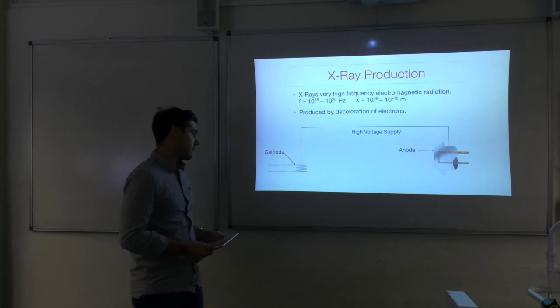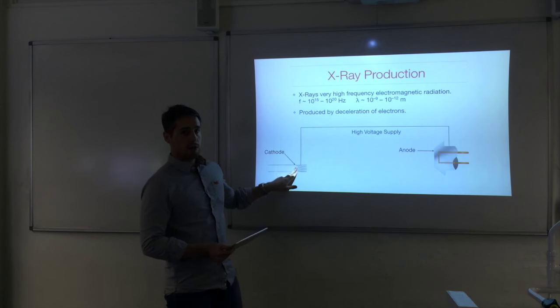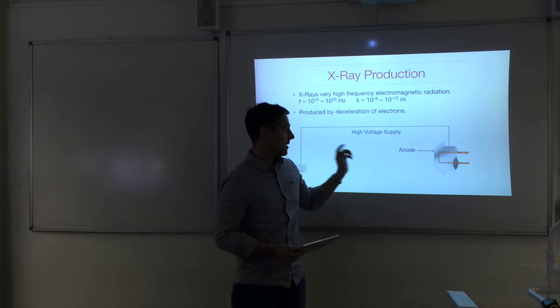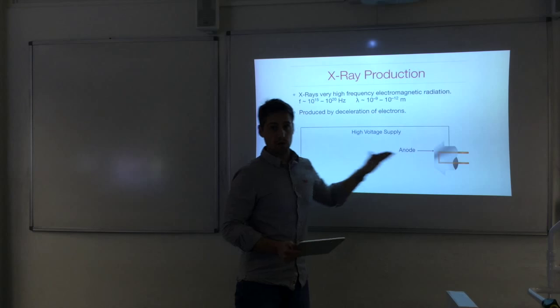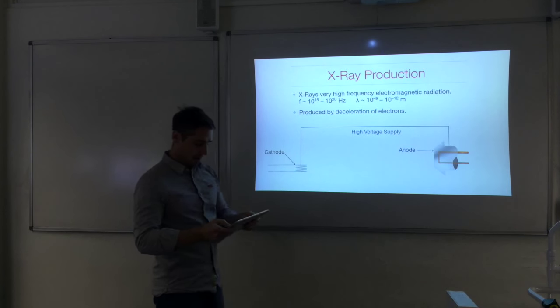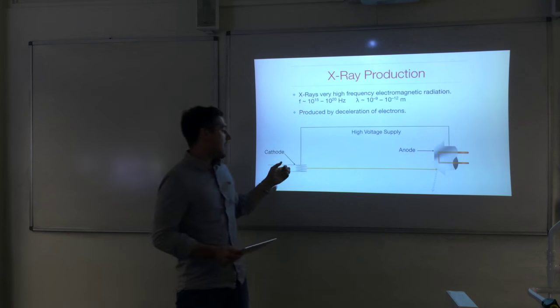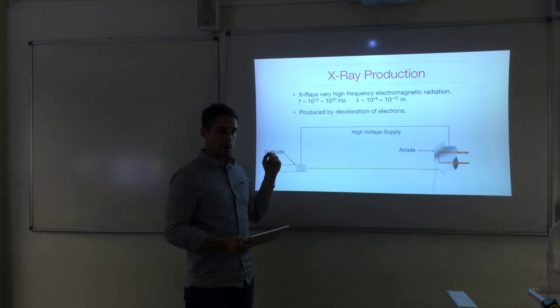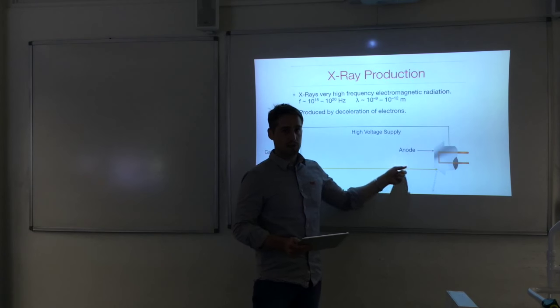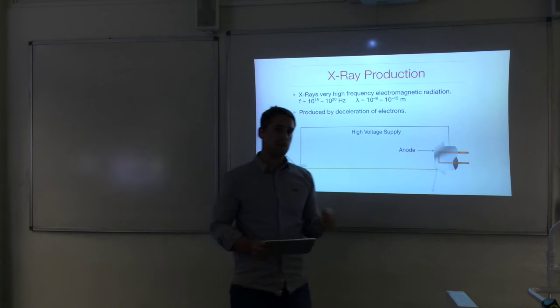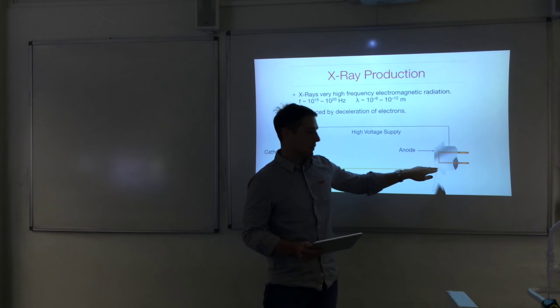In an x-ray tube there are three primary components: the cathode, the high voltage supply across cathode and anode, and the anode — sometimes called the target — because we'll be firing electrons at it. Electrons are produced at the cathode by a process called thermionic emission. This all takes place in a vacuum so that the electrons are not obstructed going from the cathode to the anode, where they are accelerated to a very high speed and crash into the target metal, usually tungsten, experiencing a large deceleration.